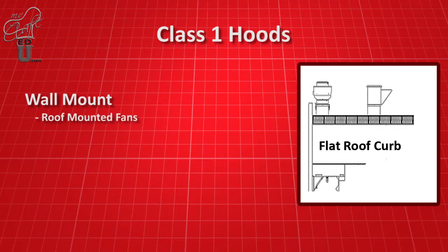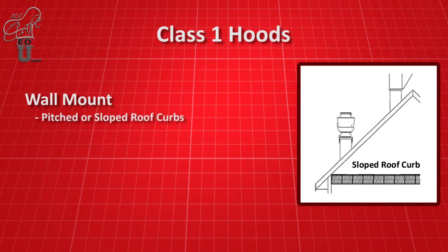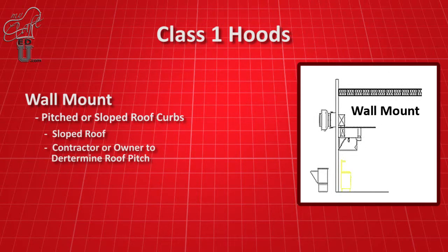Roof-mounted fans and curbs are available in two styles: flat roof curbs and sloped roof curbs. Flat roof curbs are of the same design as wall curbs, but mounted on a flat-style roof for fan mounting. Sloped roof curbs are used in applications where the building or structure has a pitched roof. Now, when specifying sloped roof curb applications, you will need to speak with the contractor or owner to determine the roof pitch so the hood manufacturer can ship the correct curb with your exhaust hood and fans.